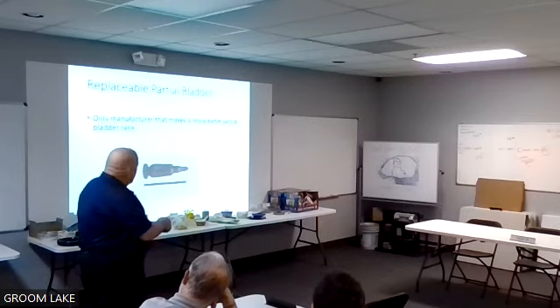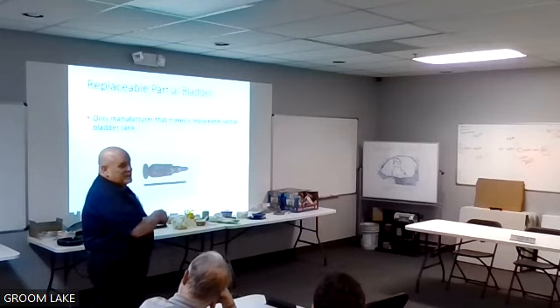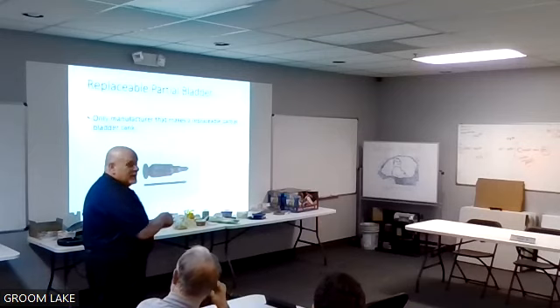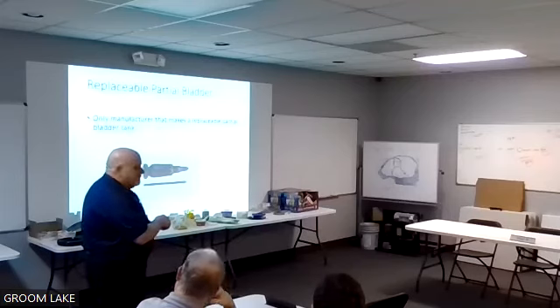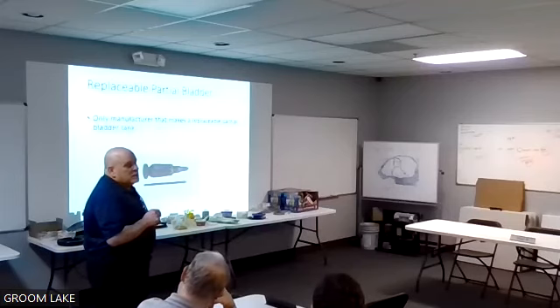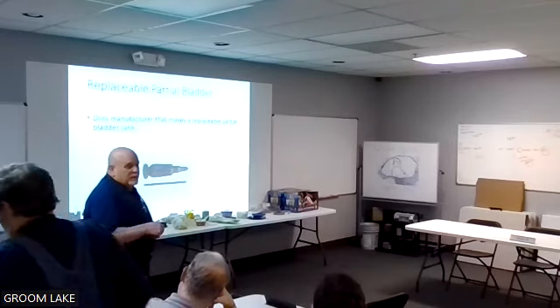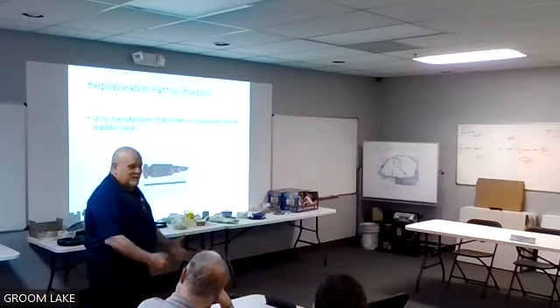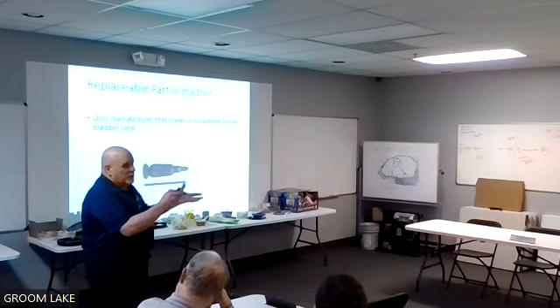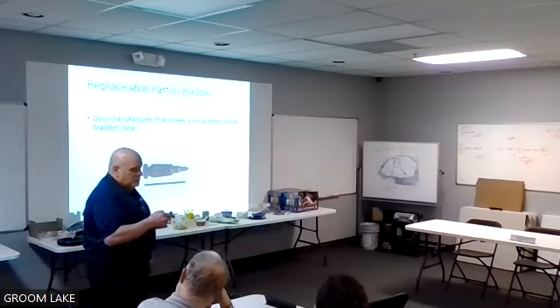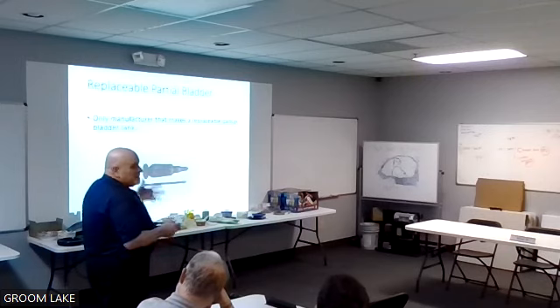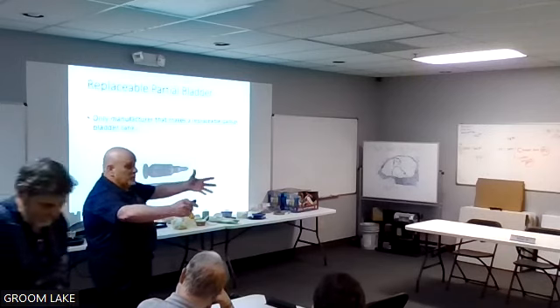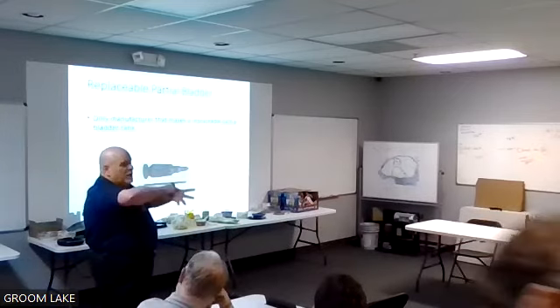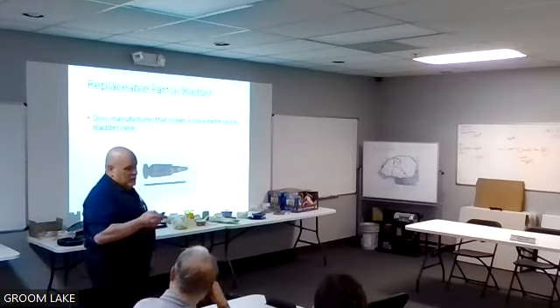If I have 12 gallons in here and I need 20 gallons of acceptance with a 34-gallon tank, go to the next bigger tank. My expanded water volume has to fit in the bladder. Okay? That's all the water will take, and the rest is all for that air cushion. That's why it's a 34-gallon tank with a 12-gallon acceptance. As it expands, I'm only going to make 12 gallons more water. When I hit 200, I'm not going to overextend that bladder.